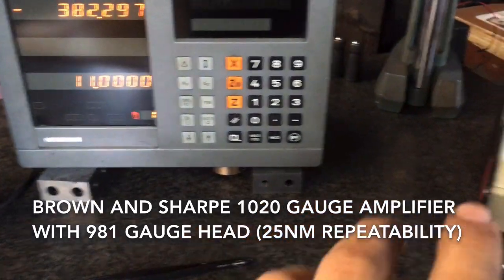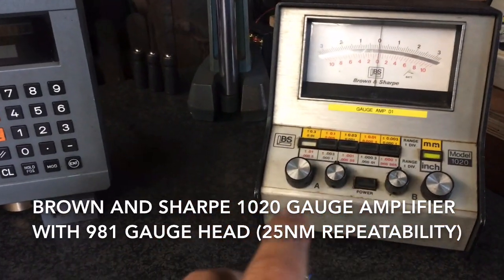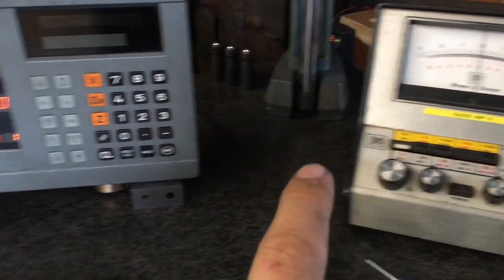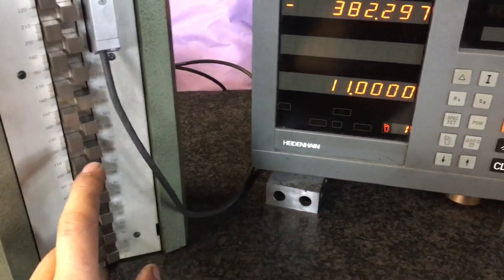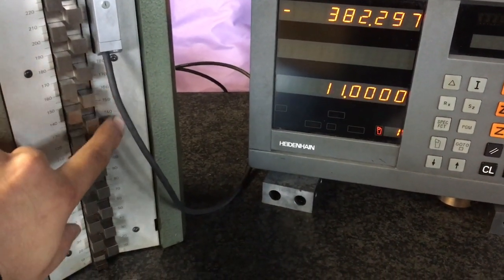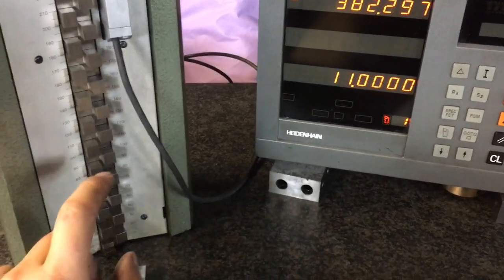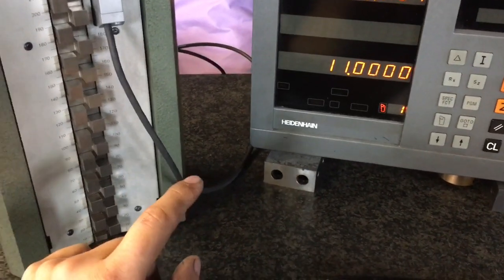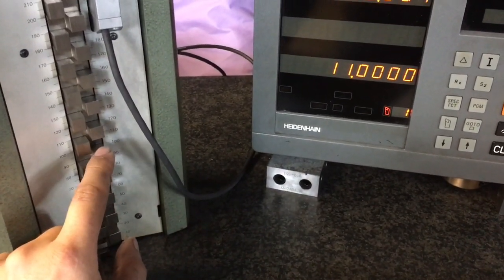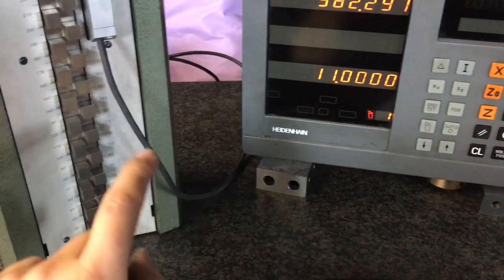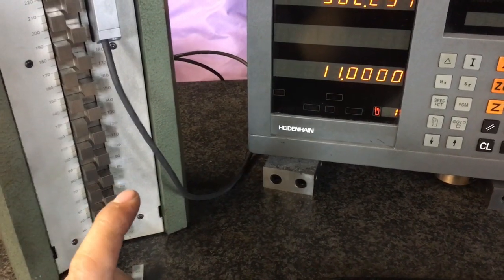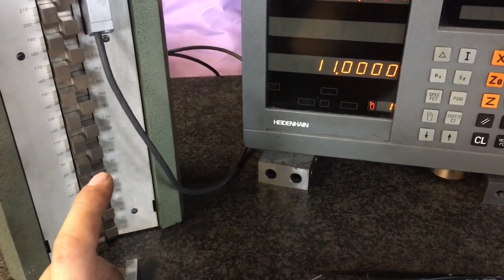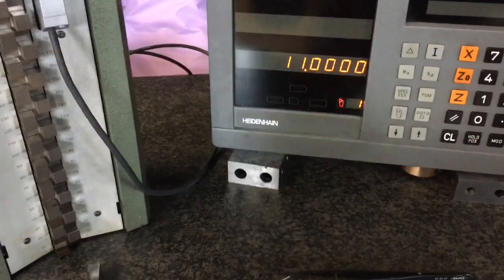As I said it's not a dimensional situation here, it's a repeat reading situation. This may not give you exactly 0.1 micron the dimension you want, but when you're going to probe it with your DTI or your LVDT and you turn it on zero, this is repeating really well. So when you take your zero on your part and you put it on your height master, it's going to repeat as good as it can be. And I'm going to show you what can be the problem.